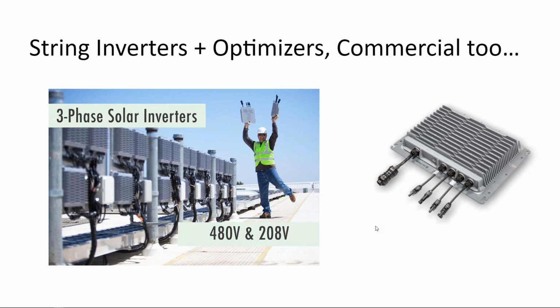If you're on the most recent National Electric Code updates, you now need to start putting these behind the solar panels themselves to meet rapid shutdown requirements. Now, from about 2017 back, there's interpretations where you could say, well, maybe that's not what's intended, but the code has been driving towards module level shutdown on rooftop applications for some time now.